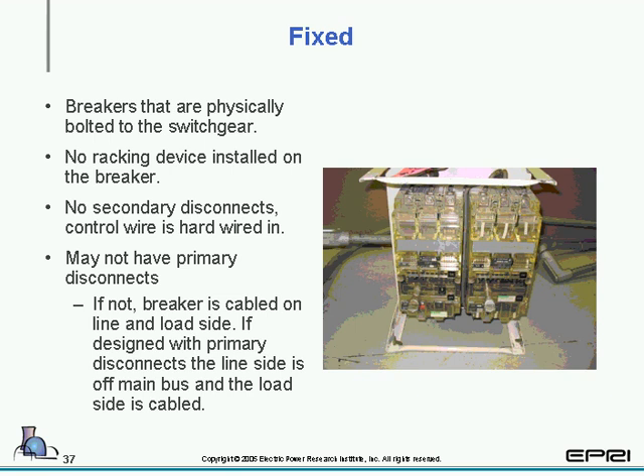First one is a fixed. Breakers are physically bolted to the switchgear. There's no racking device associated with them. No secondary disconnect, control wiring is hardwired in, and may not have primary disconnects. If it does have primary disconnects, most of the time they are bolted to the primary side, and then the secondary side is cabled in.